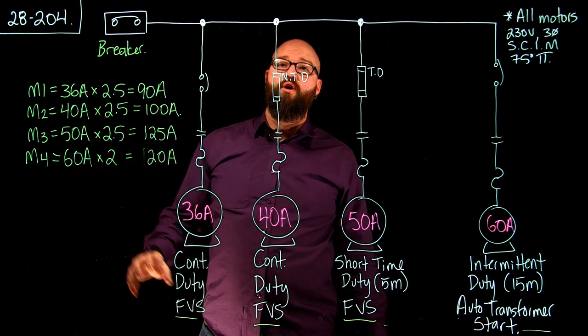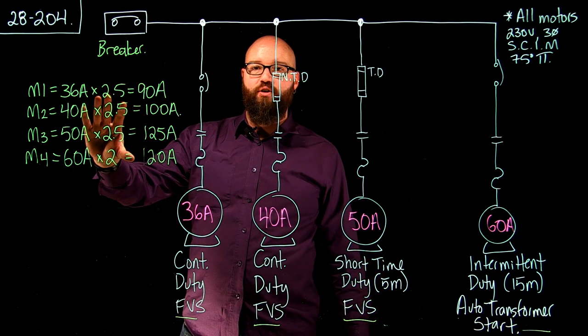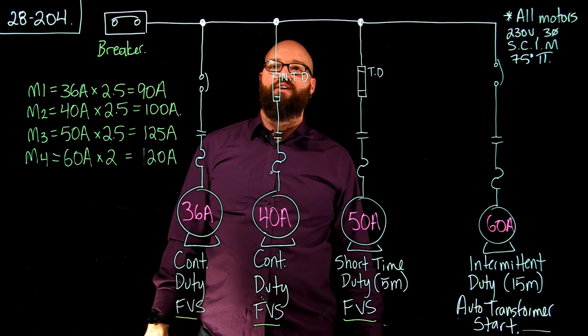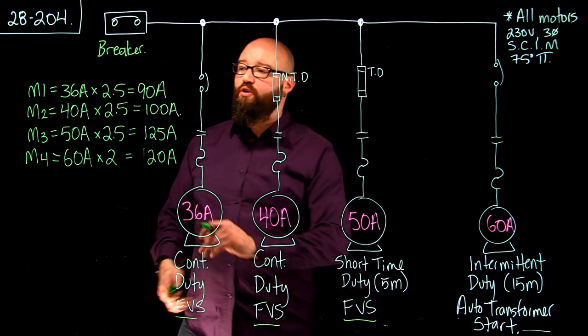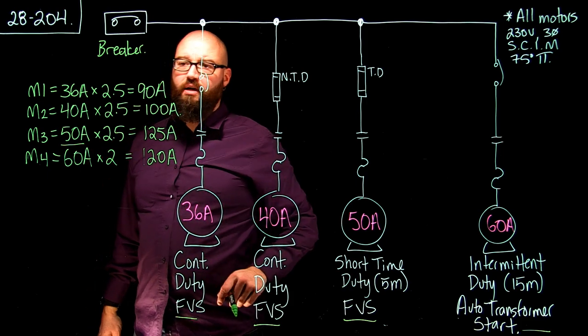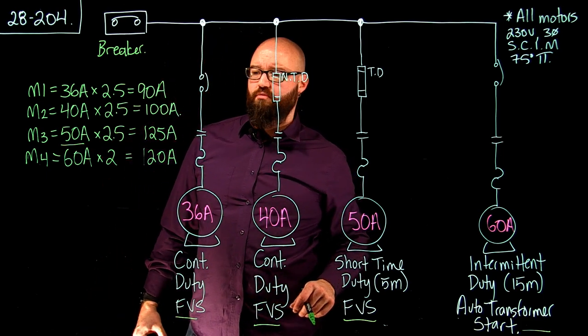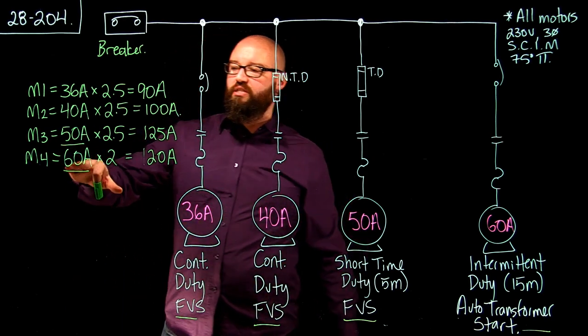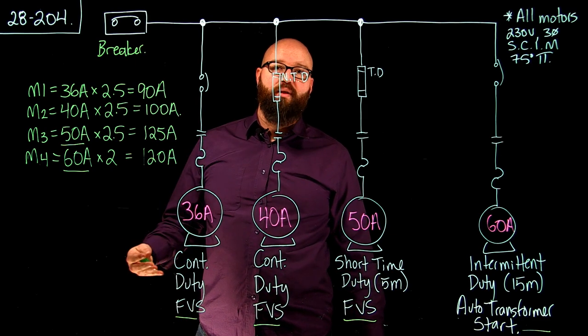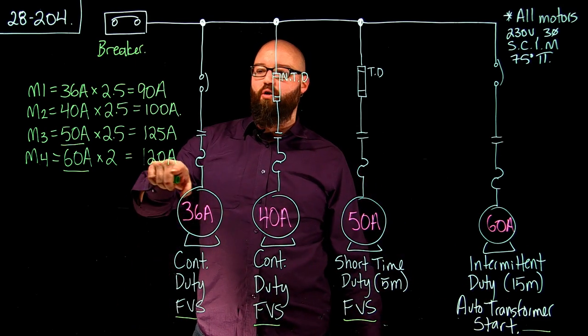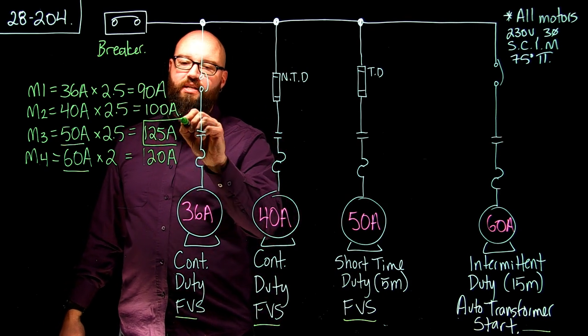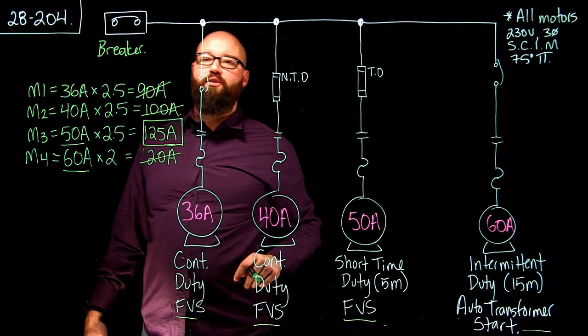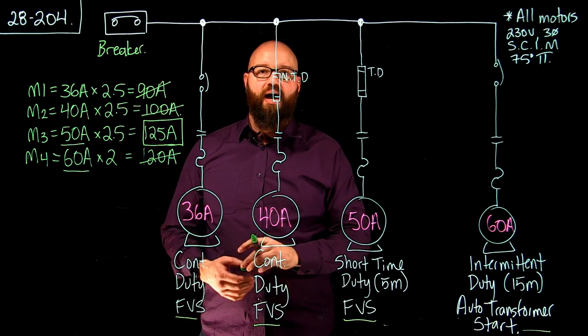The whole point of this is to determine which of these motors will have the highest calculated value, using the main overcurrent device as the determining factor for the multiplying factor. Even though we have a 50-amp FLA and a 60-amp FLA, you would think the 60-amp FLA would win. But because the multiplying factor for the auto-transformer start gives a smaller calculated value, the number that actually wins is 125 amps. At this point, we discard all other calculated values — we only used them to determine which one was highest.